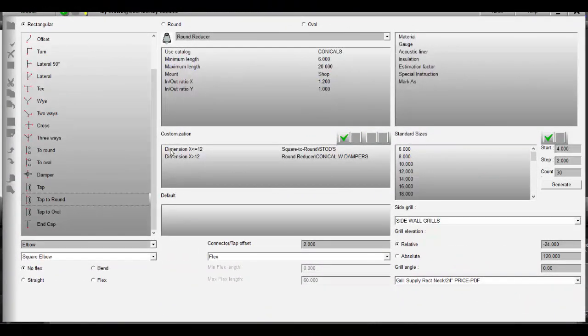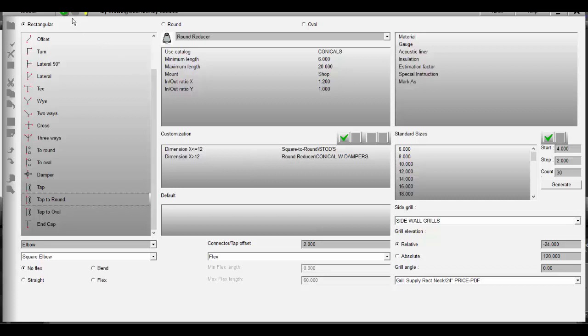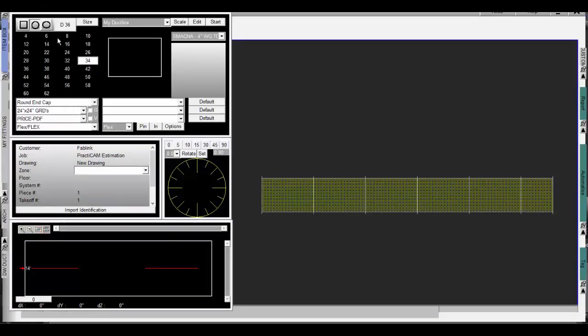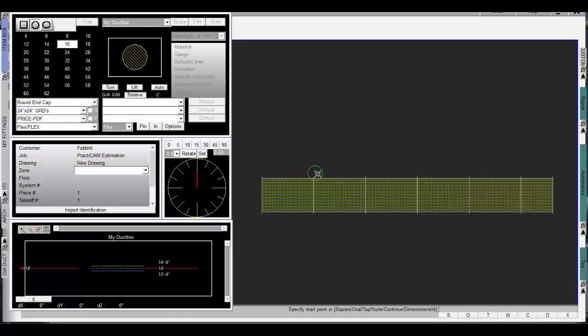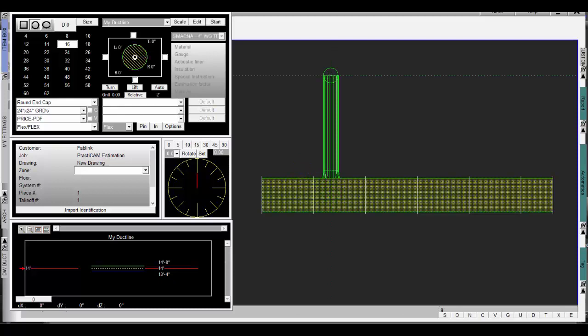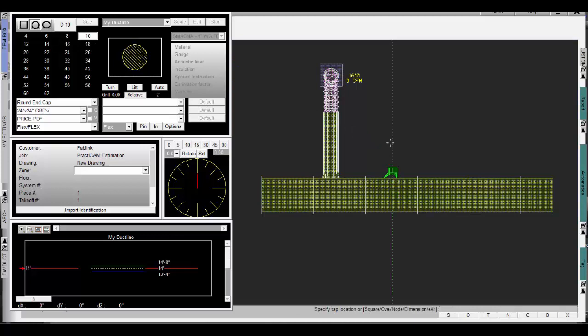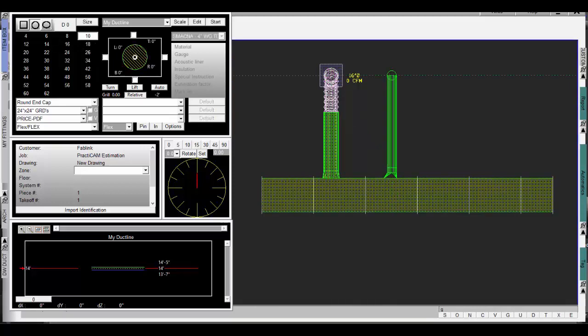Now we will demonstrate logic driven routing. Looking inside our Ductline settings we see we've set STODs to be drawn when we draw below 12 inch and conicals with dampers to be drawn when we draw over 12 inch. This is just one example of how you can set up rules to make sure the Ductline always chooses the fittings you want when estimating or drafting. Notice here as we draw above and below our different size breaks the Ductline draws exactly which fittings we'd like to use.